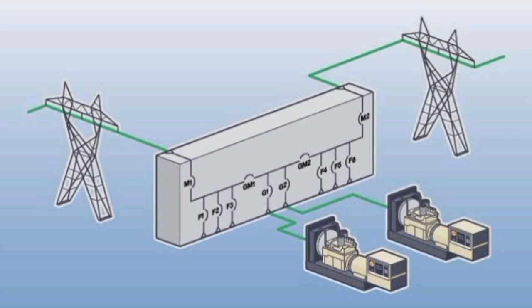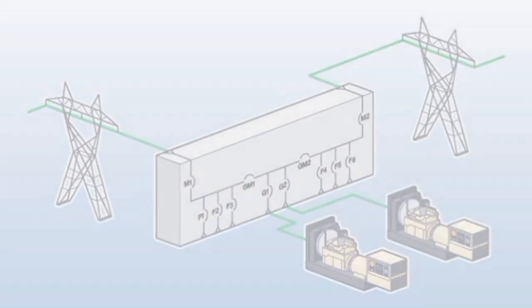If the facility requires N generators to operate, the +1 unit protects against a single generator failure. An Uptime Tier 3 design includes redundant capacity components like extra generators but may not include fully redundant distribution paths.